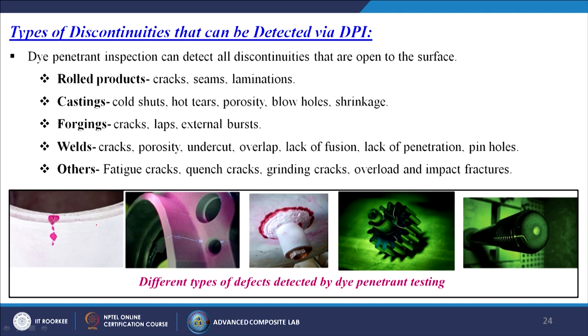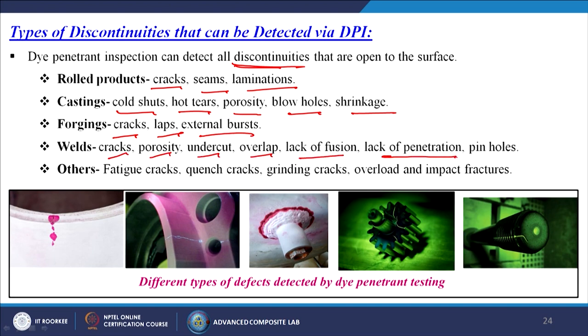DPI can detect all discontinuities open to the surface. In rolled products: cracks, seams, laminations. In castings: cold shuts, hot tears, porosity, blow holes, shrinkage. In forgings: cracks, laps, external bursts. In welds: cracks, porosity, undercut, overlap, lack of fusion, lack of penetration, pinholes. Other defects include fatigue cracks, quench cracks, grinding cracks, overload and impact fractures.